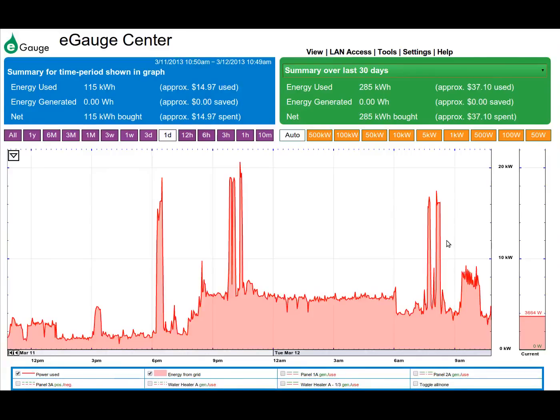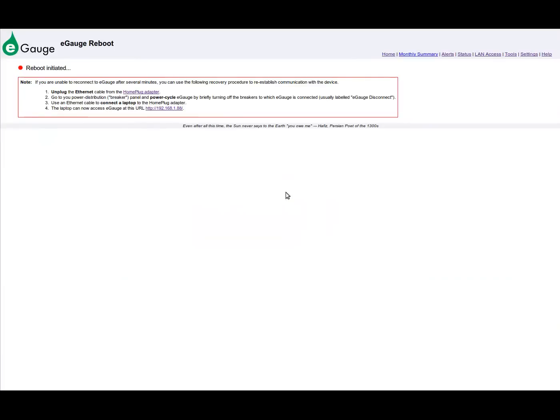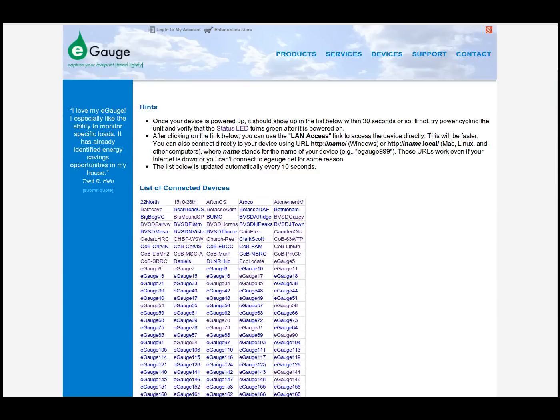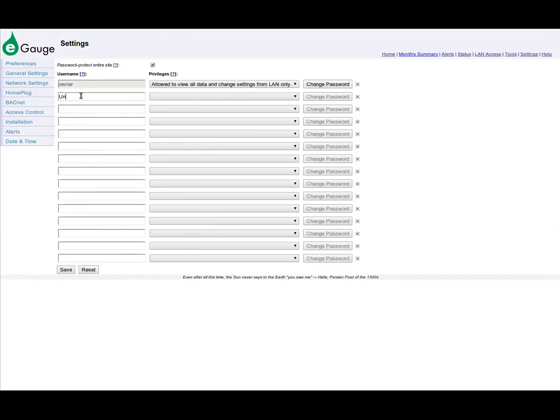In a sub-metering situation, you may want to limit each tenant's view to only their own information. This can be easily done with the views that were created. From Settings, Access Control, check Password Protect Entire Site. Note that when Password Protect Entire Site is selected, this device will no longer be listed on the Public Devices page at eGauge.net/devices. Next, a user should be created for each view with the same name as the view. User and view names are case-sensitive. For permissions, choose Restricted to User Name View. Save the settings.